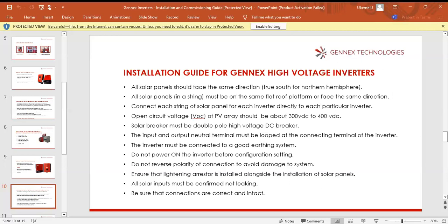You are advised to operate at that high voltage. The higher the voltage within the normal range, the better the performance and the experience you get from this system. The solar breaker must be a double pole high voltage DC breaker for PV. With this high voltage, you need to cut off both positive and negative when you switch off the PV. It's very important, and the breaker has to be high voltage. See, it's the normal rating.